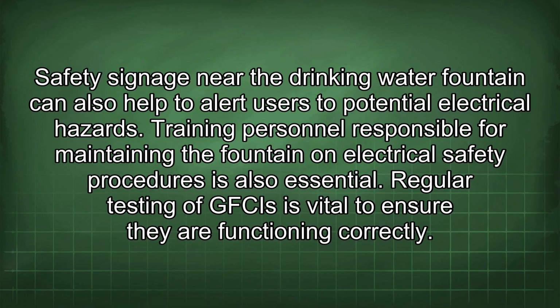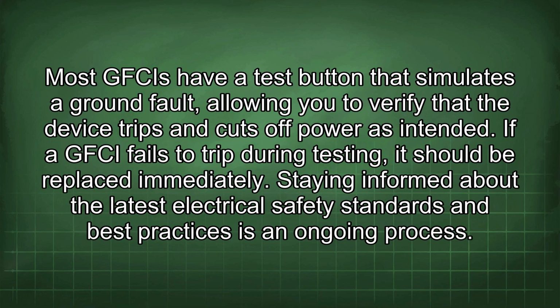Regular testing of GFCIs is vital to ensure they are functioning correctly. Most GFCIs have a test button that simulates a ground fault, allowing you to verify that the device trips and cuts off power as intended. If a GFCI fails to trip during testing, it should be replaced immediately.